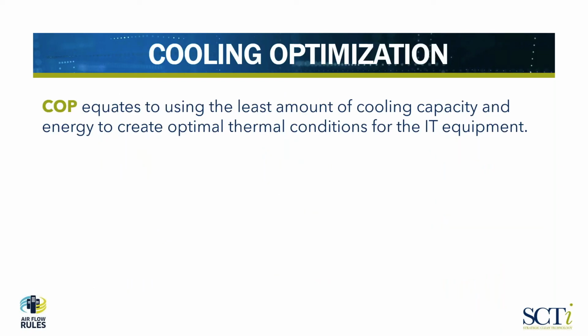We refer to our program as cooling optimization. What does that really mean? Essentially, it equates to using the least amount of cooling capacity and energy to create an optimal thermal condition for the IT equipment. Even though our focus is on cooling, we realize IT equipment is the critical aspect of the data center—that's why the data center is there, that's why you have one. So our objective is to give that IT equipment as good an environment as possible to operate in.